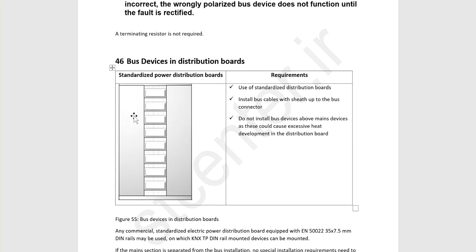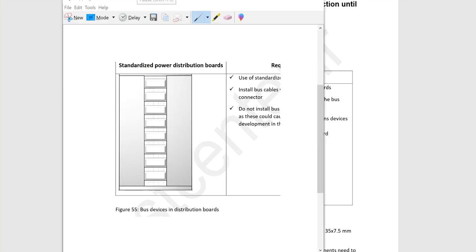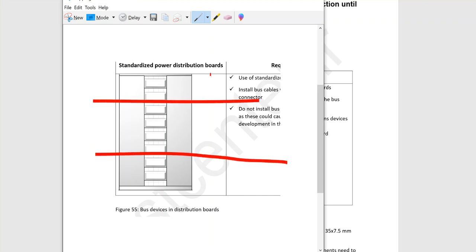So if I want to install devices in one electrical cabinet, I can divide it into three parts. In one part I put the contactor and the power supply units, for example 230 V with 12 V DC output, that generate heat. I put other devices like a KNX dimmer or KNX power supply unit here, with less power generation. And I put devices like fan coil actuators, relay actuators, and so on here, with no power generation.